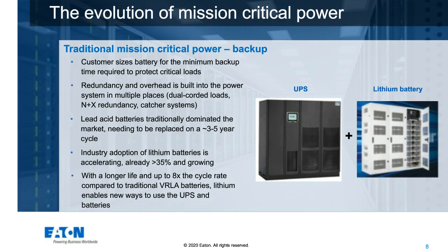So let's review the evolution of mission-critical power. UPS system and battery, it primarily is there to provide power conditioning and battery backup in the event of a problem with the incoming utility power. We also keep in mind that over the previous 3 or 4 decades, the tolerance for power anomalies of the critical devices we're supporting has become greater, lessening the need for the UPS to provide power conditioning, but it still does, along with that battery backup. But the big reason to have a UPS for a lot of clients is simply to get them onto their generator and condition the power from that point forward.